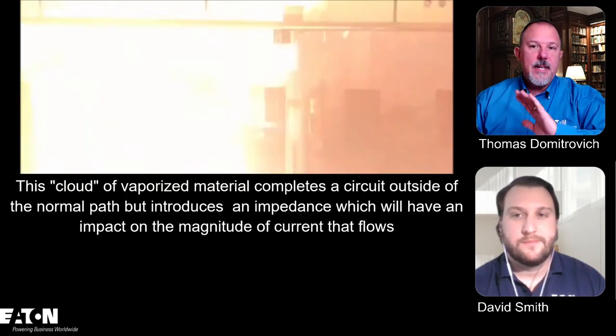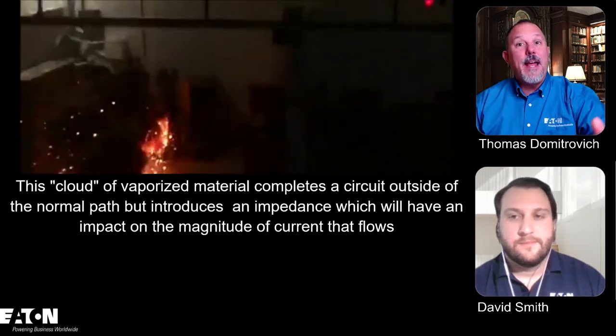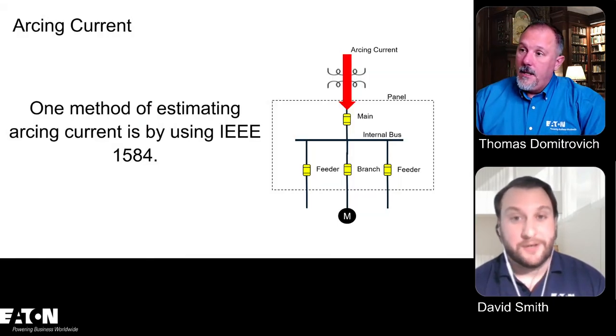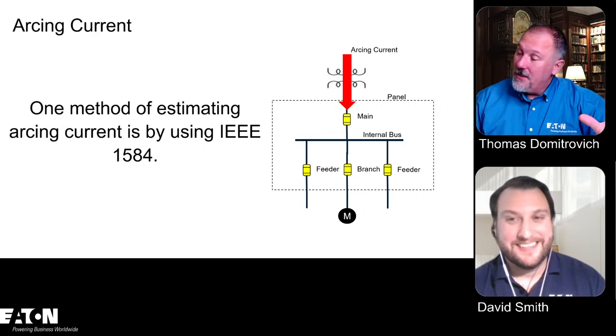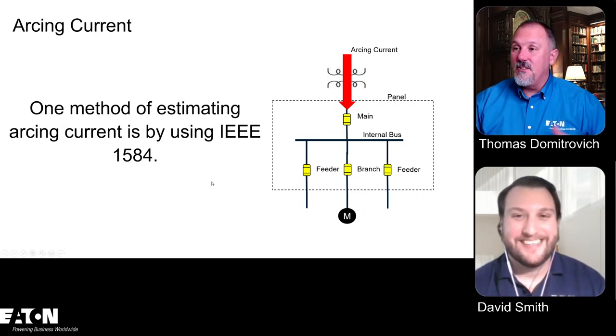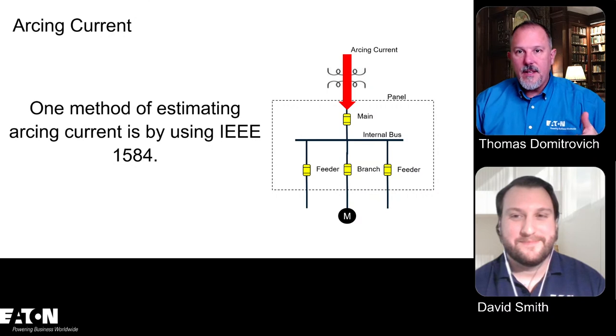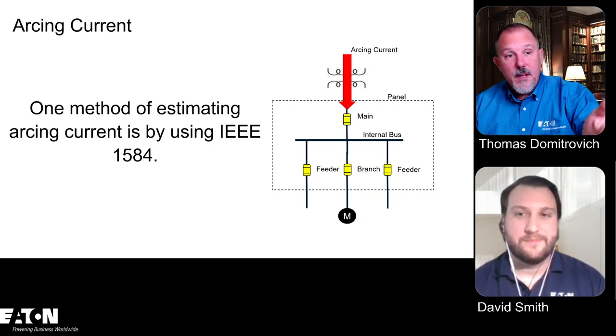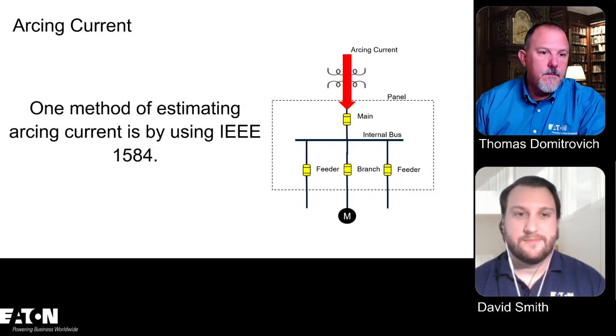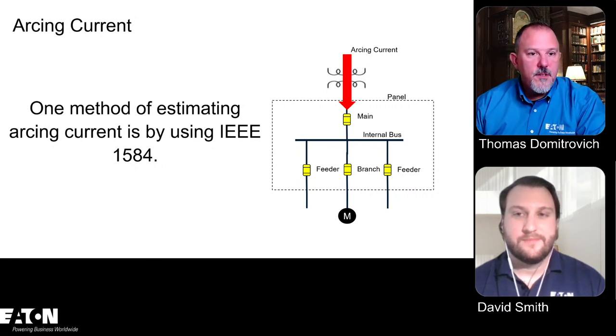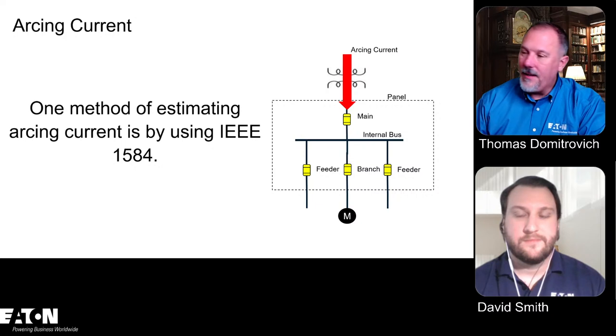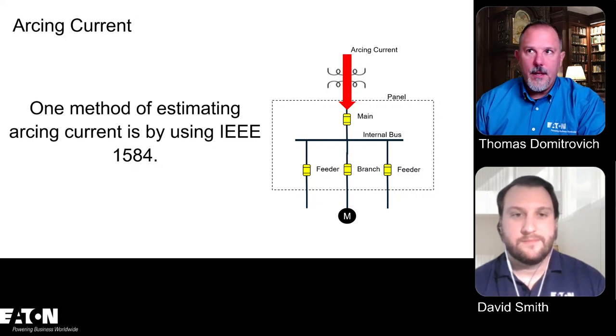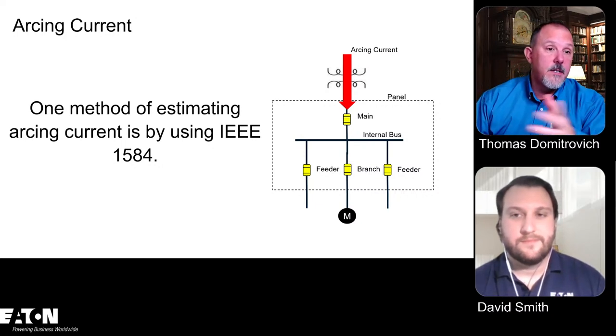So it completes, and basically your current is flowing through the air. It's arcing. That's absolutely right. So it's outside of the normal path. So one method that we use is IEEE 1584. Now, the other method, I see Ross, how would you define arcing current since there are multiple methods to determine arcing current? 1584, Ralph Lee, Ross, you're right.